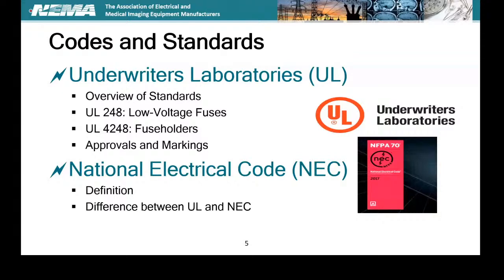And of course, the listing marking itself. And we've got some UL approvals and the markings. This is what we're looking for. We've got listed fuses. They comply with all the requirements inside that standard. General use, applies to the NEC, and bears the listing marking. So these are the markings you want to look for on that product.